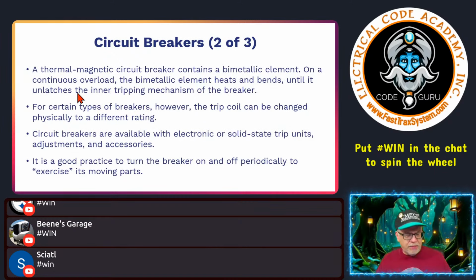Now, all these different types of circuit breakers and their characteristics and how they operate. You are probably well aware of these, but you have thermomagnetic circuit breakers, and what they contain is a bimetal element. It's like a bar, and when you heat that circuit breaker up under load, excessive load, short circuit, ground fault protections, all those things, typically the bimetal component works on overload. As it heats up, this bimetal will bend, and as it bends, it gets to a certain point where it releases the latch.